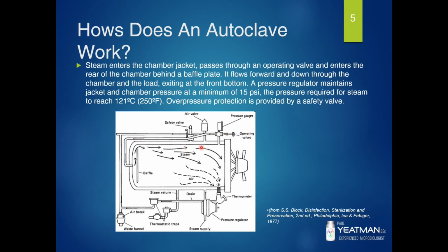As the steam enters the autoclave, it pushes the air out. There's a pressure regulator that maintains the jacket and the chamber pressure at a minimum of 15 pounds per square inch, which is the pressure required for steam to reach 121 degrees C, and the overpressure protection is provided by a safety valve. So as I talked about in an earlier slide, once the steam comes in, there's a seal, and the increase in pressure locks the seal down, which effectively seals the unit automatically. And after the autoclave cycle, everything gets evacuated, so the steam goes out, air comes back in, and then you'll check temperature traces and whatnot to determine whether or not the cycle was actually valid, which I'll explain why that must be done later.